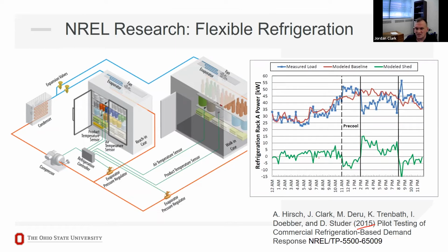It might look something like this: if we know there's going to be a need for some load shedding at, let's say, 2 o'clock—in this case we had a period from about 2 to 8 where the grid operator wanted us to shed load—so we overcooled a little bit, making all the product a bit colder than it normally hung out at, and then turned things off. We really just turned up the set points so the compressor never kicked on. The temperature inside the case rises a little during that, but never hits the bound where it has to turn back on.